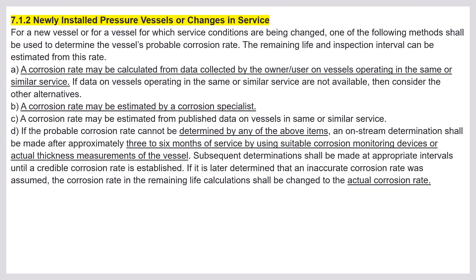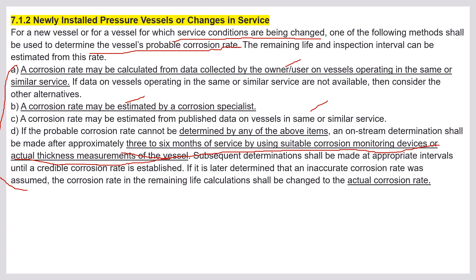For newly installed pressure vessels or vessels with a change in service, one of the following methods shall be used to determine the probable corrosion rate: the corrosion rate may be calculated from data collected by the owner/user; estimated by a corrosion specialist; or estimated from published data on vessels in the same or similar service. If the probable corrosion rate cannot be determined by any of the above, an on-stream determination shall be made within approximately three to six months of service using suitable corrosion monitoring devices or actual thickness measurements.